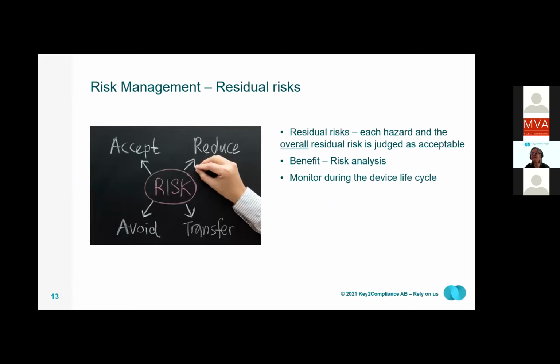The residual risks need to be analyzed to be acceptable in each individual risk, but also residual risks together. Are they still judged to be acceptable? A risk-benefit analysis needs to be included and concluded that the benefits outweigh the risks with using the device. It's not enough with just a statement. You need to include an analysis of all the benefits and the residual risks and the impact it might have. It needs to be a discussion behind the statement. The risk management is to be updated when necessary during the whole life cycle of the product.